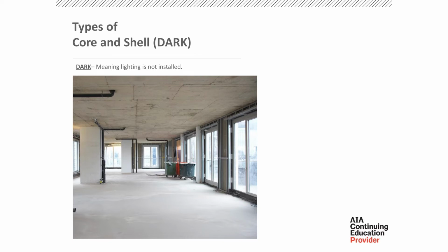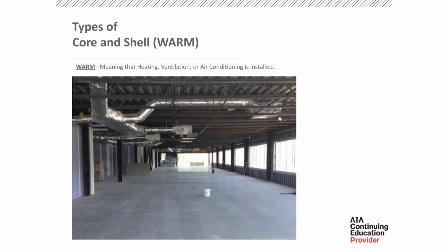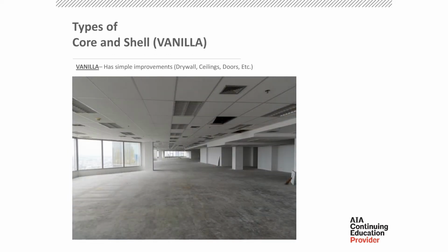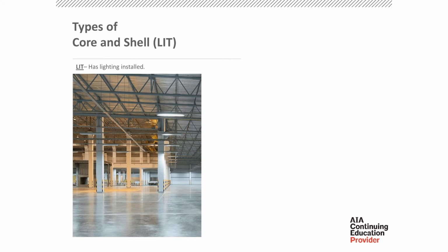Now you have dark, meaning the lighting is not installed. That's just for the lighting. Then you have warm, where you actually have the HVAC. Then you have vanilla, where you have the walls and everything else, and possibly you'll have lighting, but you can actually see a floor being built out. So core and shell lit refers to the actual lighting, where they actually have the lighting installed.